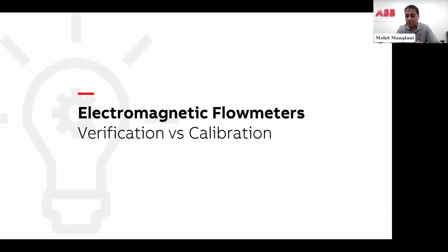Verification versus calibration. So great conversation. So you specified a mag meter, everything's working. You might be using it for billing purposes, whatever it might be. Somebody challenges you and says, well, prove to me that device is accurate, right? So mag meters, we already use it for operations. We use it for controls. We use it for chemical dosing. We use it to determine what we need to do to our process, whether it's controlling a valve, controlling chemicals, whatever it might be, filling or batching, right?